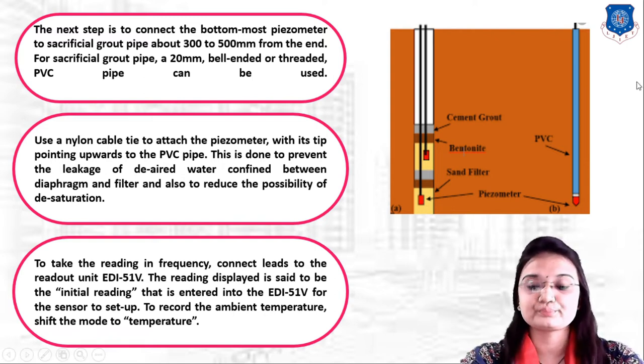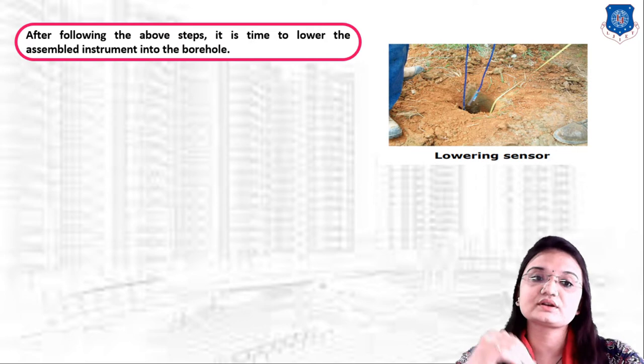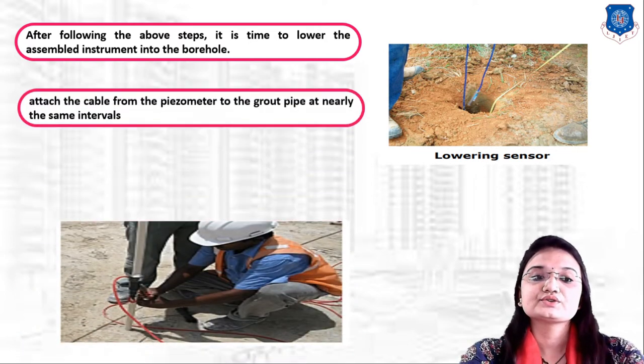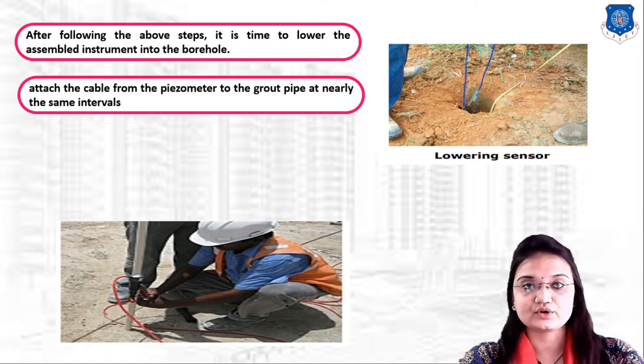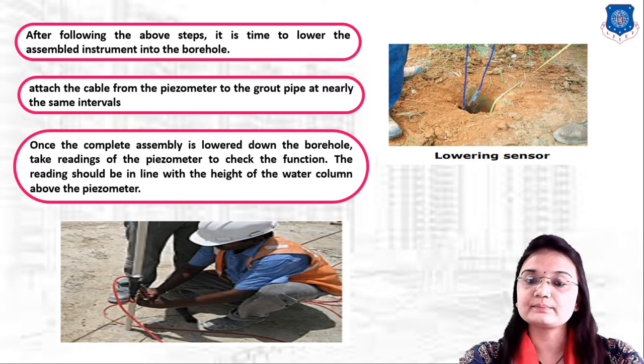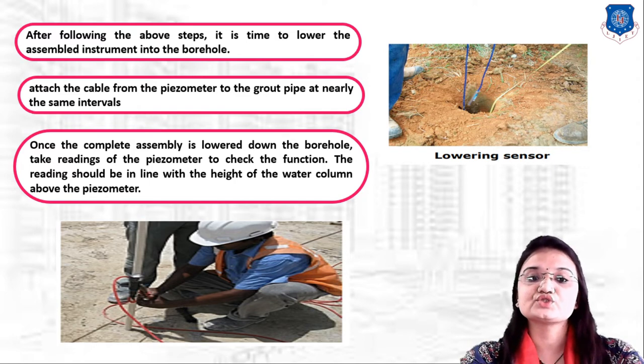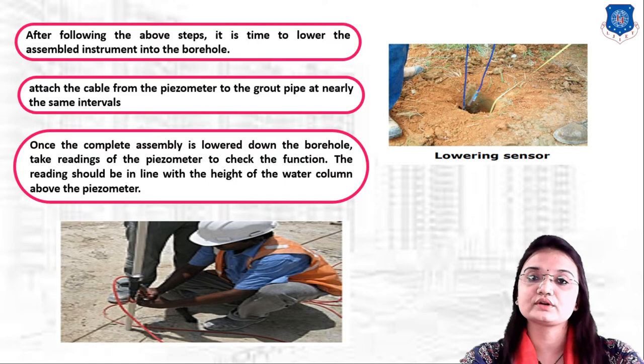After following the above steps, lower the instrument into the borehole. Attach the cable from the piezometer to the grout pipe at nearly the same intervals. Once the complete assembly is lowered into the borehole, take a reading to confirm the piezometer is functioning. The reading should be in line with the height of the water column above the piezometer.